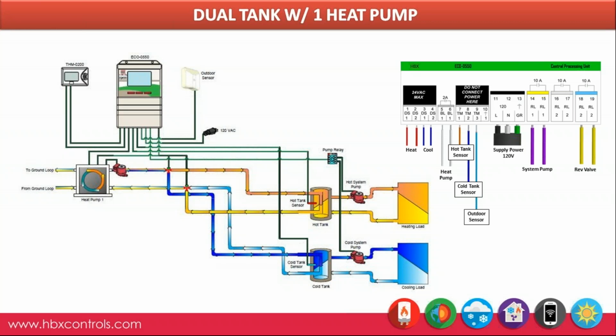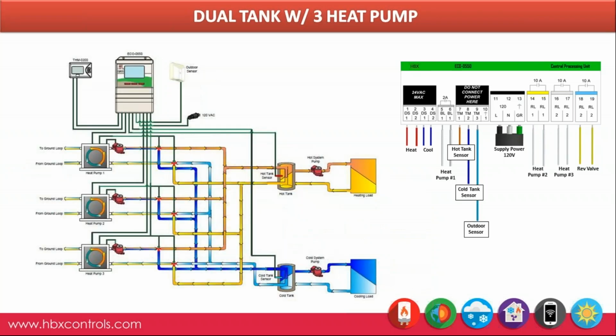Supply power is 120, and since we're only utilizing 1 heat pump here, we can control a main system pump, and your reversing valve is always the last relay of that Eco 550. Again, if we're doing the same setup but with 3 heat pump stages, you would see that pins 14, 15, 16, and 17 are for our additional second and third heat pump stages.